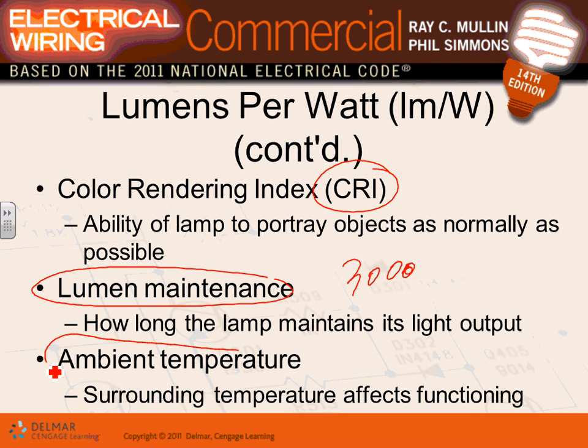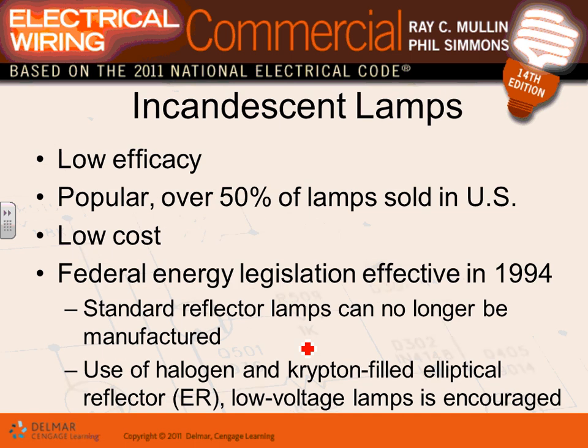Ambient temperature is a major factor — the surrounding temperature affects the function of lamps. Certain fluorescent lights will not work in Minnesota outdoors at 25 below zero; the ballast will not fire under those temperatures. You have to have a special type of ballast that allows operation in extreme cold — especially for outdoor fixtures or freezer applications. The ambient temperature will affect the performance of these fixtures.